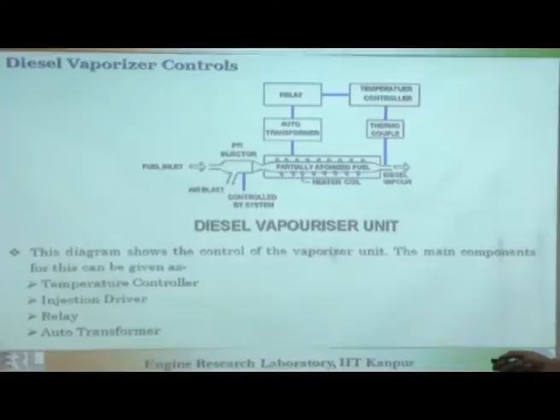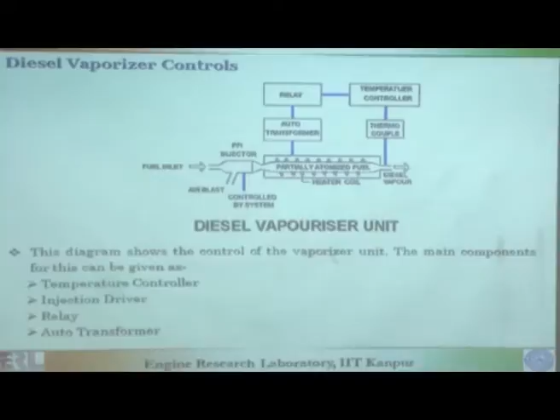And here you have put a thermocouple to see what is the temperature at which your fuel vapors are coming. This is connected to a temperature controller, then it is connected to a relay and then to a transformer which is controlling the heater coil. So basically the heater coil temperature is also controlled. This diagram shows the application and control of the vaporization unit. Main components are temperature controller, injection driver, relay and auto transformer.